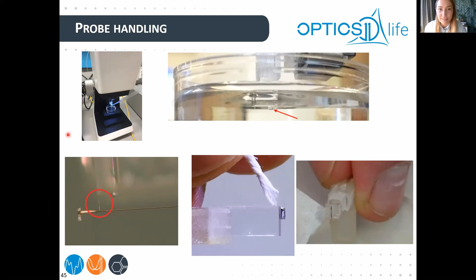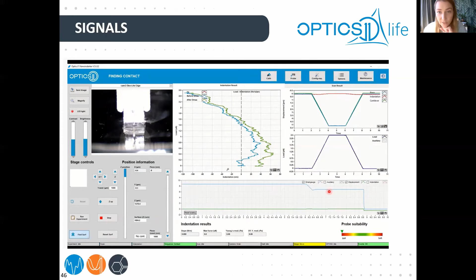For the new users, I will just quickly explain the signals that I'm going to talk about further on. The first ones are the signals in the main screen. We have a piezo signal in blue, and the green one is the cantilever signal. Now you also have interferometer signals. The main measure signal is the same as this green one, but from the interferometer. When you indent on the sample, what you will see here is fringes. The signal is not linear. What we measure is interference fringes. So when the cantilever bends, you see this kind of shape.